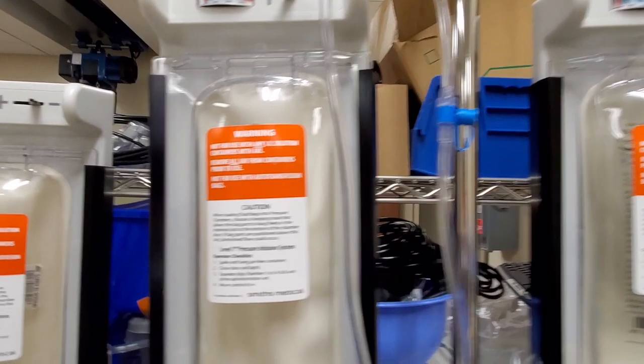Load a new saline bag. Close the lid. Pressurize it. So you guys have heard me talk about rapid infusers before. These are used to distribute infusables like blood products or saline into the patient when they're bleeding out.